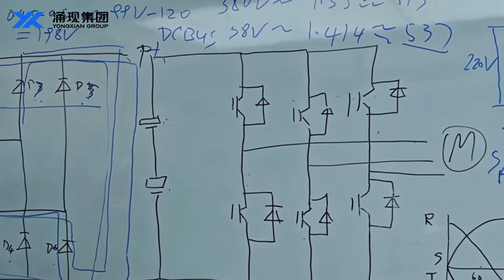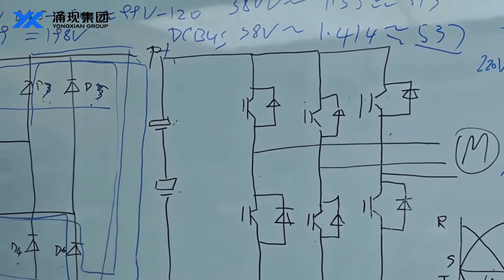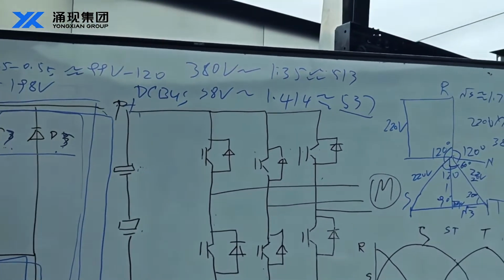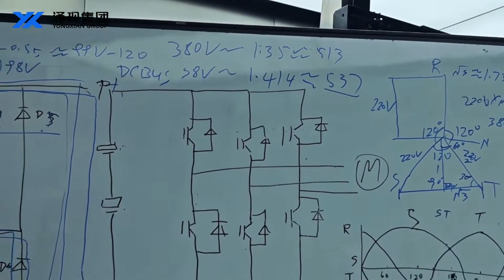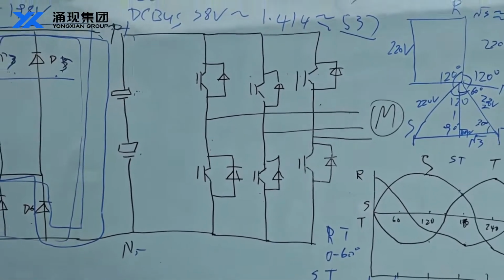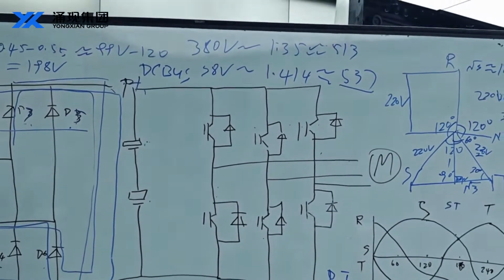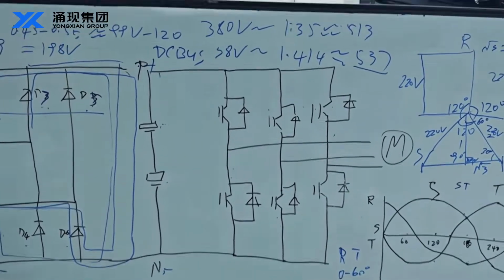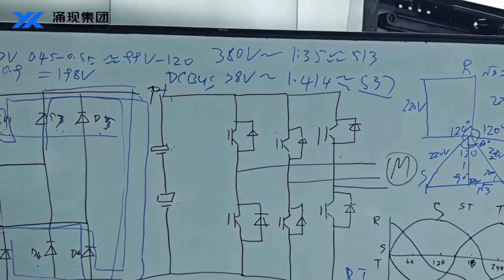A common fault we encounter is DC bus overvoltage. This fault is largely unrelated to the input power supply.